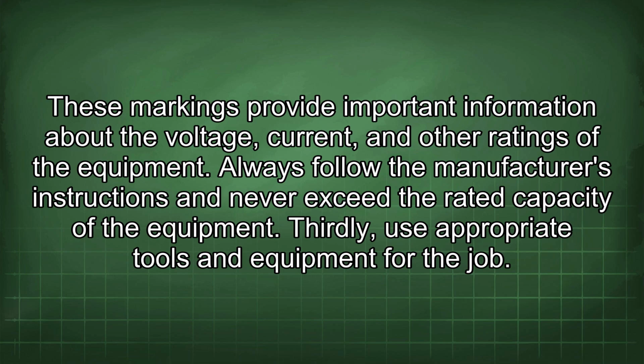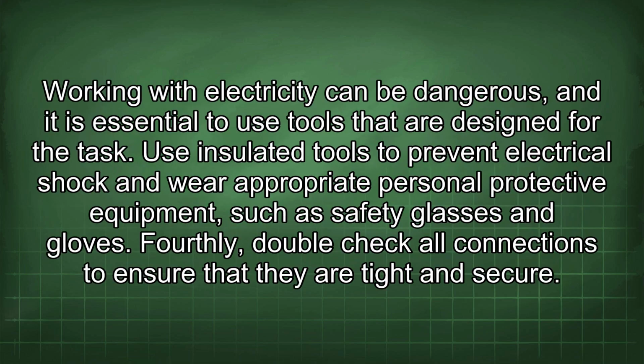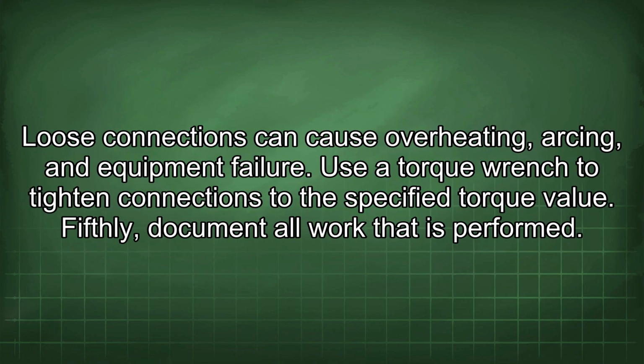Thirdly, use appropriate tools and equipment for the job. Working with electricity can be dangerous, and it is essential to use tools that are designed for the task. Use insulated tools to prevent electrical shock and wear appropriate personal protective equipment, such as safety glasses and gloves. Fourthly, double-check all connections to ensure that they are tight and secure. Loose connections can cause overheating, arcing, and equipment failure. Use a torque wrench to tighten connections to the specified torque value.